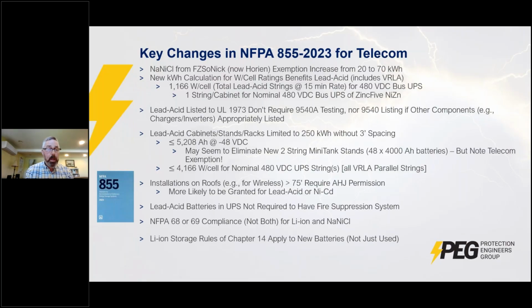For UPS applications, cells are typically rated in watts per cell, and there's a conversion from watts per cell to kilowatt hours that was made, and it actually is beneficial to lead acid. Lead acid, it turns out, the faster you discharge it, the less real power you get. So by discharging the UPS cells faster, as they typically do, or sizing them based on that, you can actually have a slightly larger UPS plant than would be permitted if it was a long discharge type plant. So it's a little bit of a relaxation, but the code still applies.